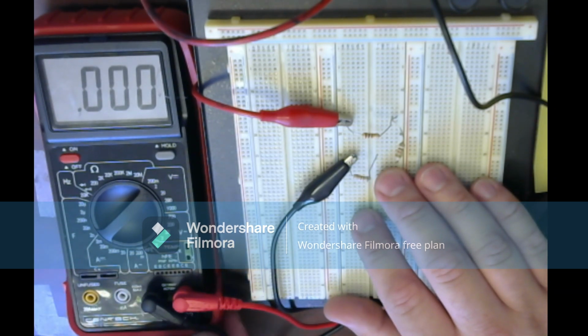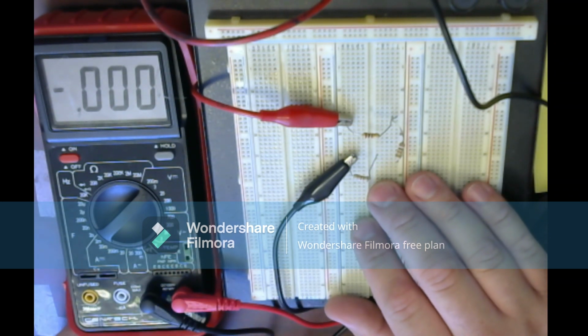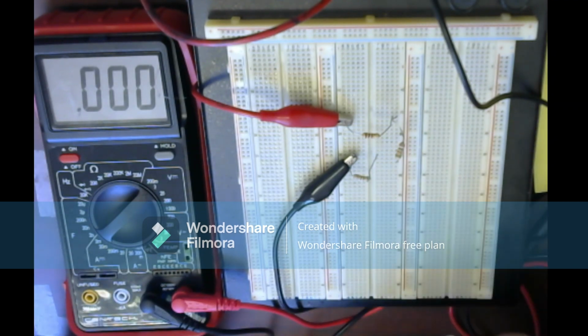My red wire is connected to the probe port that says voltage, resistance, and frequency, but I'm not after those, I want to measure current. Down at the bottom, one port says milliamps and the other says 20 amps. So I have two options: read milliamps here, or up to 20 amps here. Keep in mind we have that 200 milliamp fuse limitation — if we exceed 200, the fuse will pop. We've already checked the fuse, it should be good.